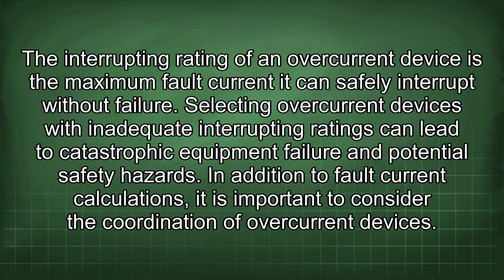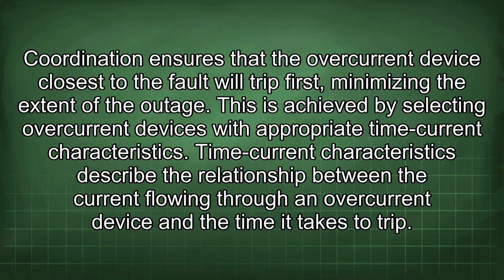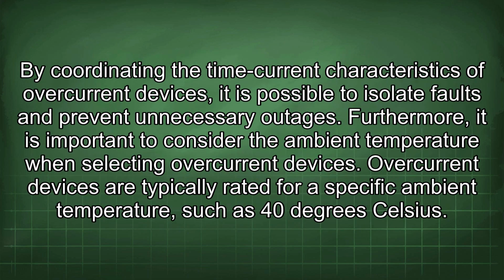In addition to fault current calculations, it is important to consider the coordination of overcurrent devices. Coordination ensures that the overcurrent device closest to the fault will trip first, minimizing the extent of the outage. This is achieved by selecting overcurrent devices with appropriate time current characteristics. Time current characteristics describe the relationship between the current flowing through an overcurrent device and the time it takes to trip. By coordinating the time current characteristics of overcurrent devices, it is possible to isolate faults and prevent unnecessary outages.